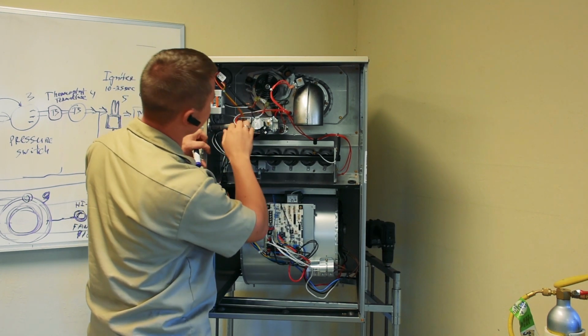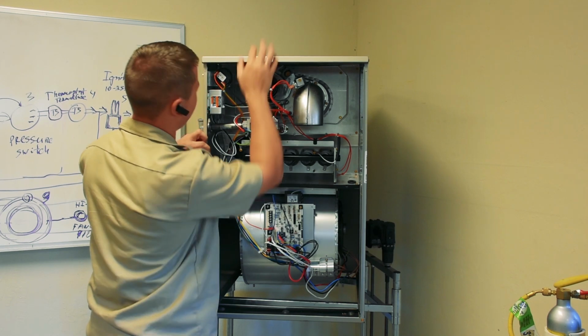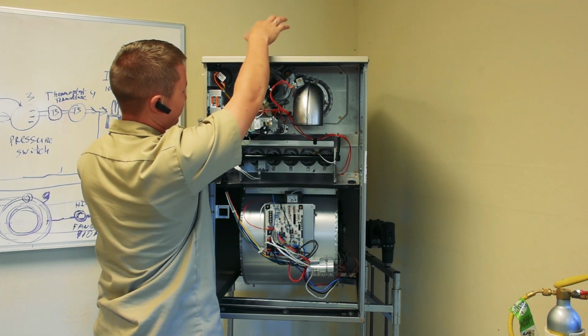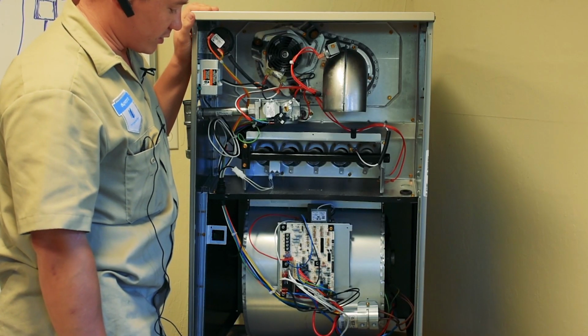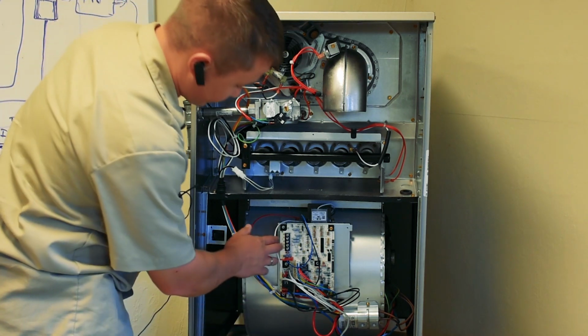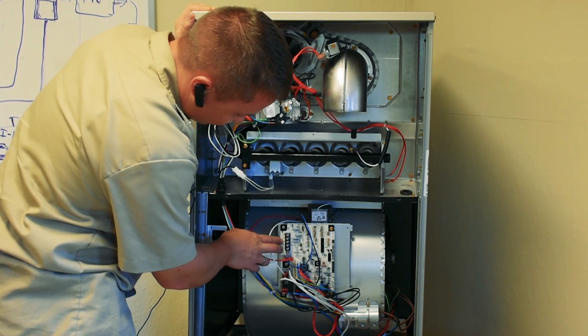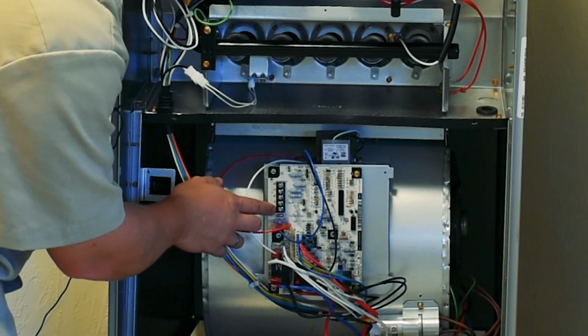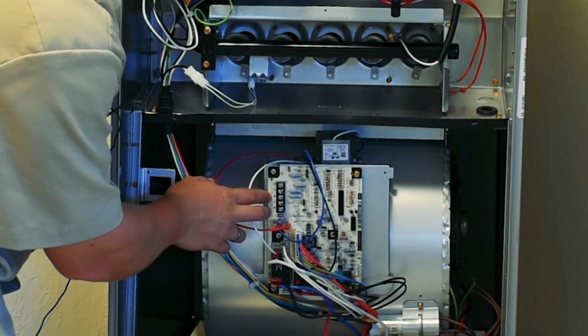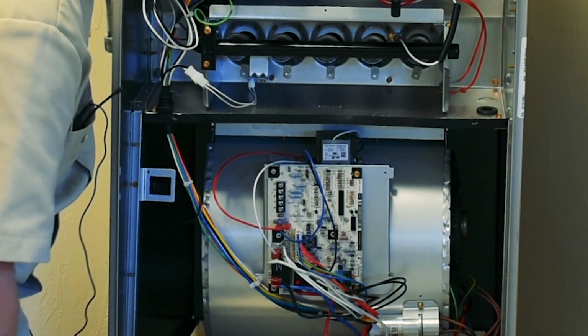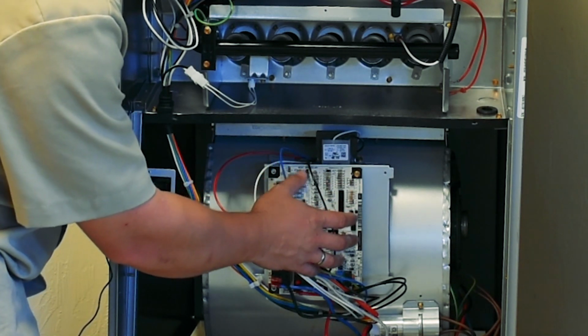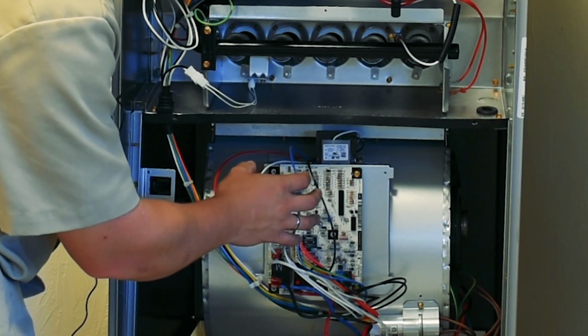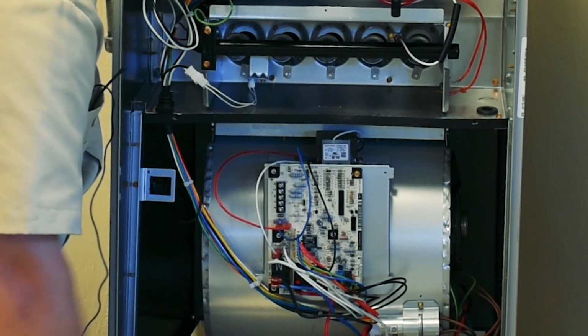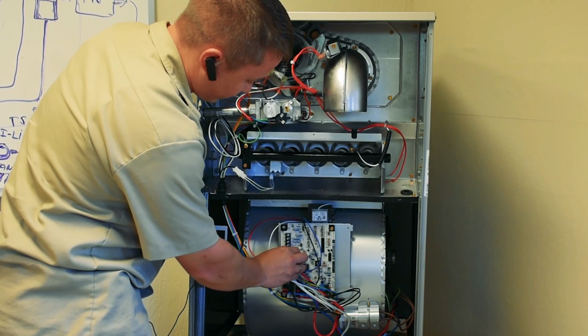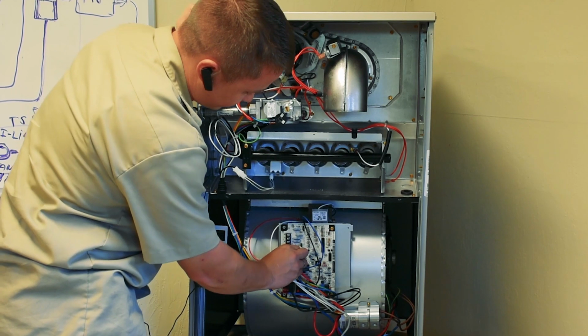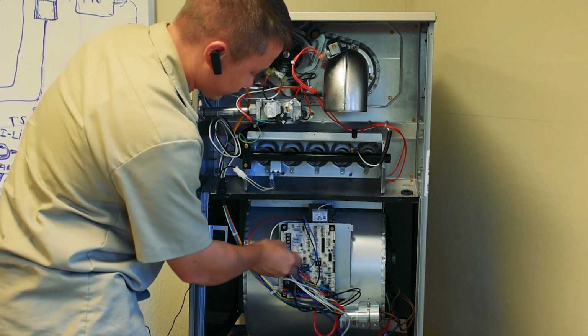Then, because here is the heat exchanger chamber, I mean the room for the heat exchanger, when you turn on the thermostat and require heat, you're bypassing the two terminals W and R. Here is the incoming for the R terminal, 24 volts AC. Okay, like I said, the control board has two circuits, low voltage and high voltage, 120 volts and 24 volts. For the 24 volt circuit, the control board also has a fuse for 3 amperes.